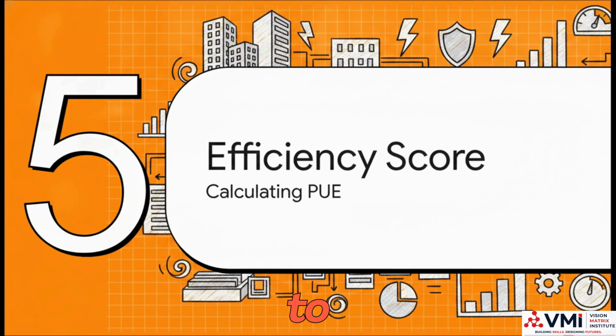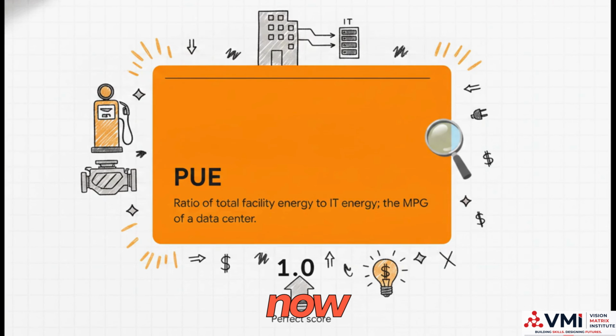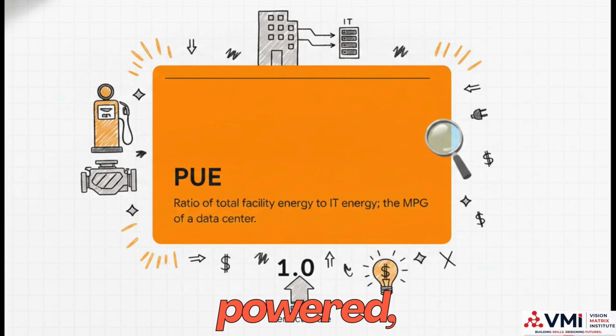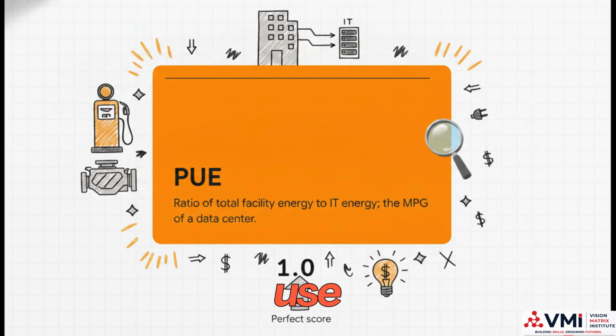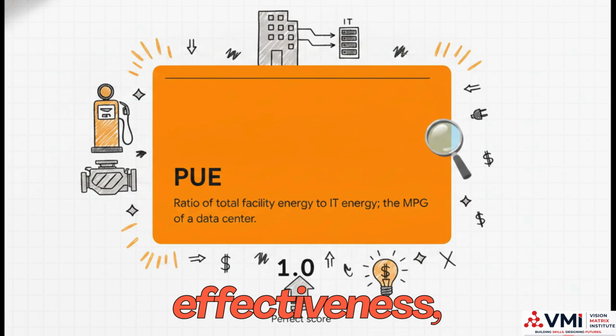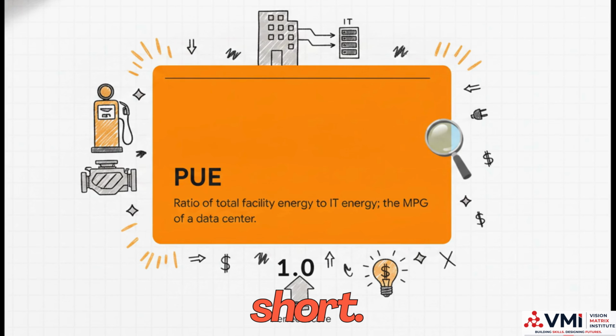Which leads us to Part 5, the ultimate efficiency score, calculating PUE. Now that our city is built, powered, and protected, how do we actually grade its performance? We use a metric called Power Usage Effectiveness, or PUE for short. It's simply the total energy the whole facility uses divided by the energy that actually makes it to the computer servers. Think of it as the fuel efficiency, or the miles per gallon, of the data center.